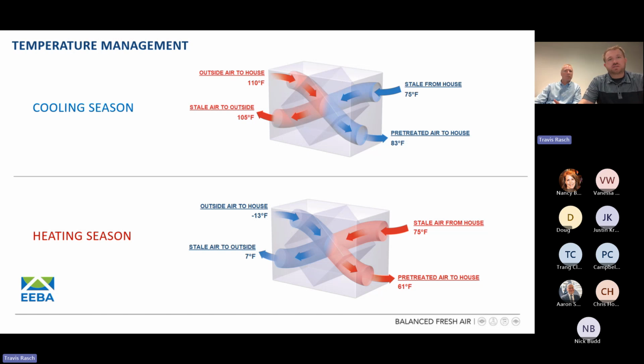The same can be said for a heating season. So we're in Minneapolis, Minnesota. It's negative 13 degrees Fahrenheit out during the winter months. We're warm in our house. The family likes it nice and hot, 75 degrees Fahrenheit. And we're going to take that negative 13-degree air and warm it up to 61 degrees just by passing it through this type of product. And so you can see, again, how simplistic it is, there are no real moving components inside these outside of highly efficient, durable blower fan motors. We're taking these air paths and making them do some work with one another. And so, again, you can see the greater the difference between the outdoor air and the indoor air, the more efficient these essentially become in our ability to deliver that much more tempered air compared to what the outdoor air conditions would be if we weren't doing any recovery.